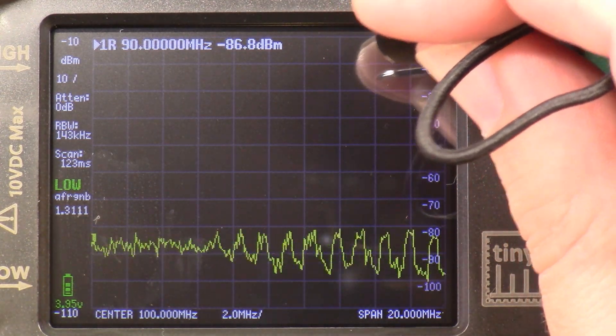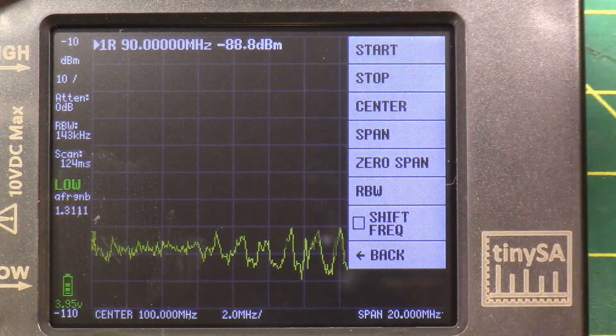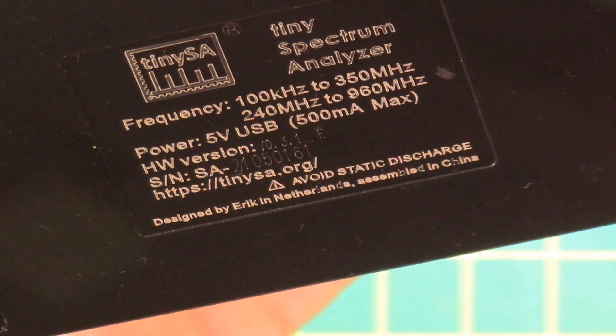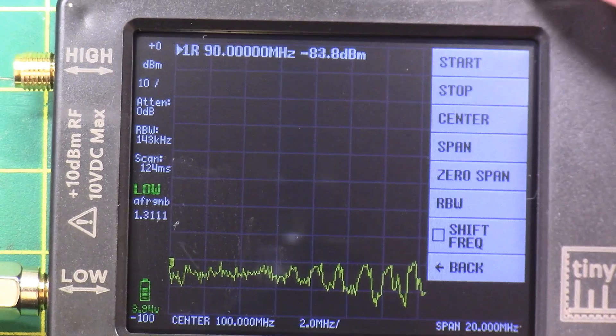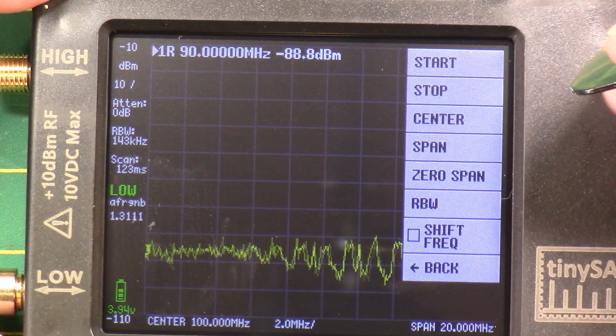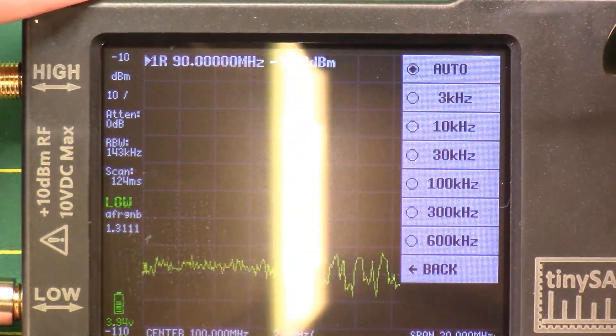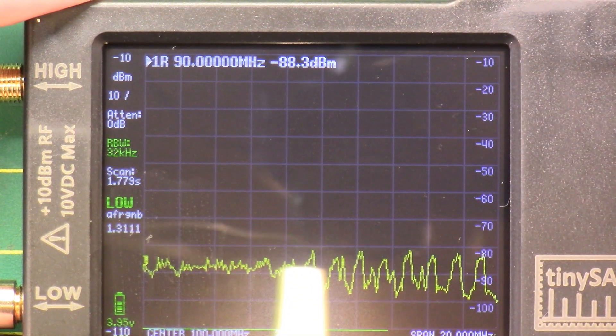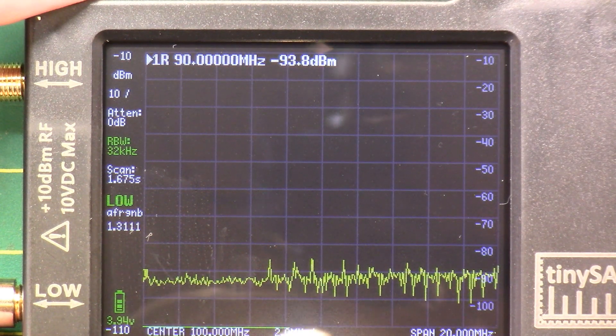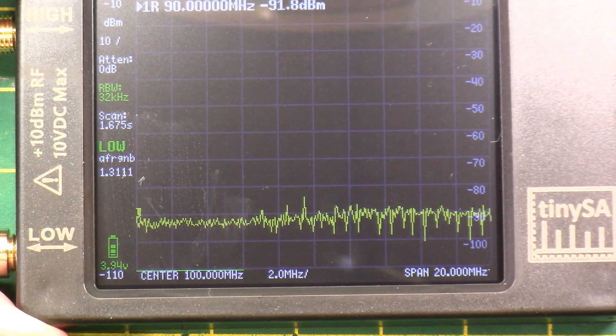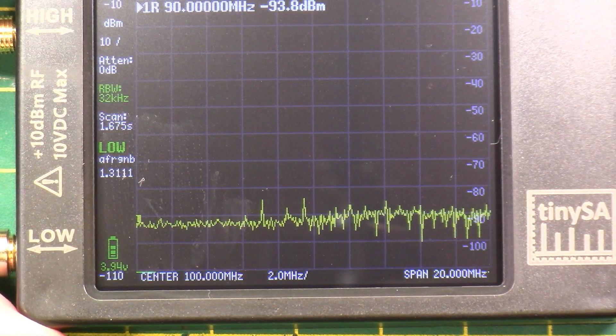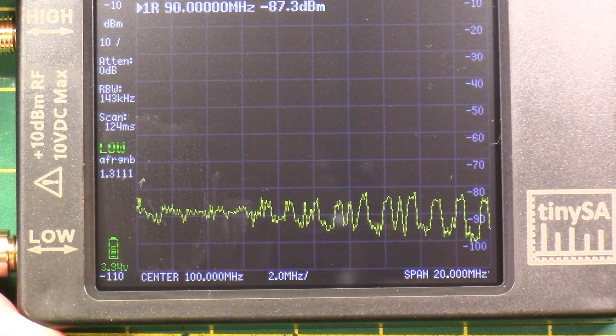Let's go even higher. Well, first off, we're on the low port and the low port is supposed to be 100 to 350. So we're definitely in the range of that 100 to 350. So we should definitely be hearing something there. Let's go RBW. What does RBW mean? Let's try 30 kilohertz. We redid the sweep. It looks like it's going to take a couple of sweeps each time. You can see the little green bar going across the bottom of the screen there. So you change the real-time analysis of it. Let's do RBW. Let's go back to auto. And now it's back to being interesting looking.